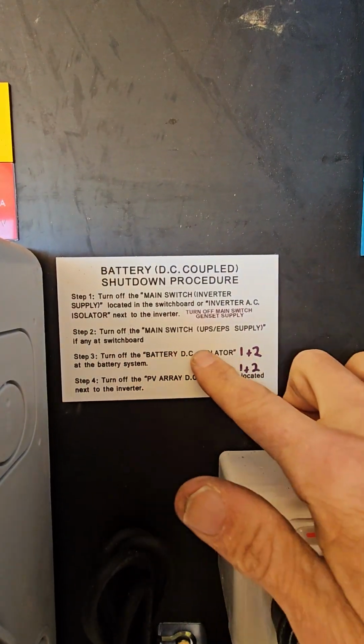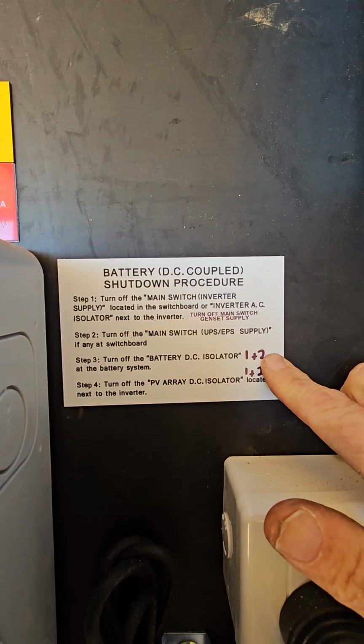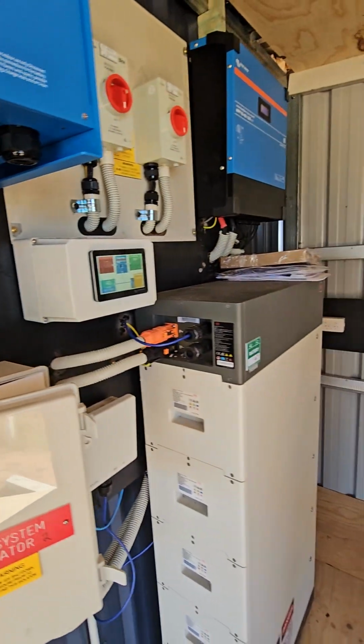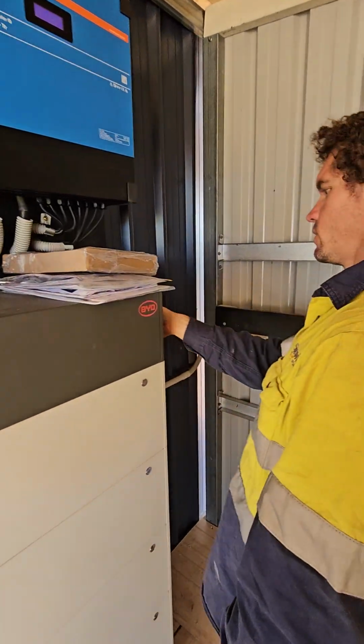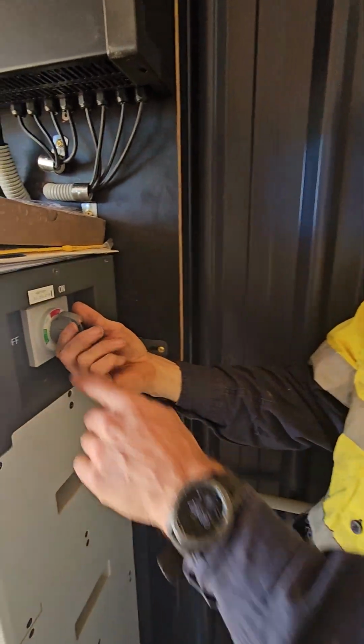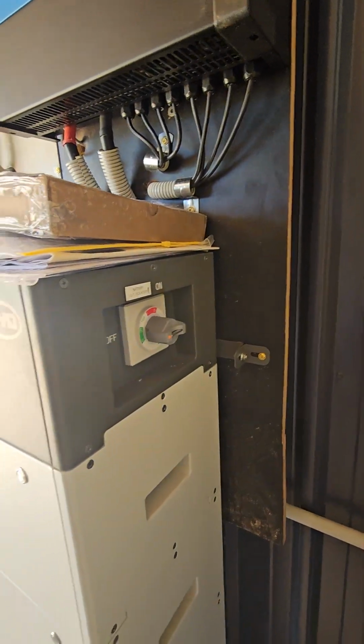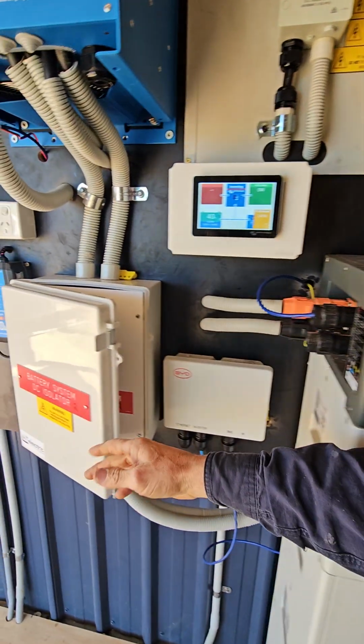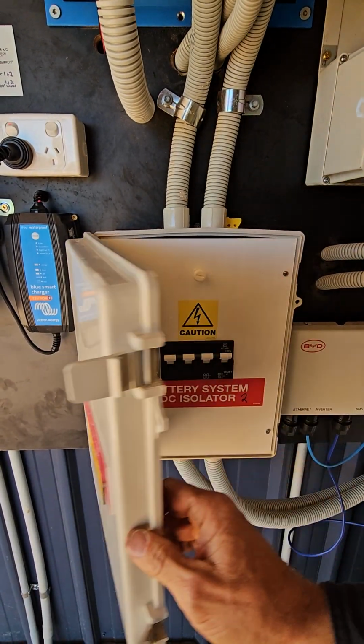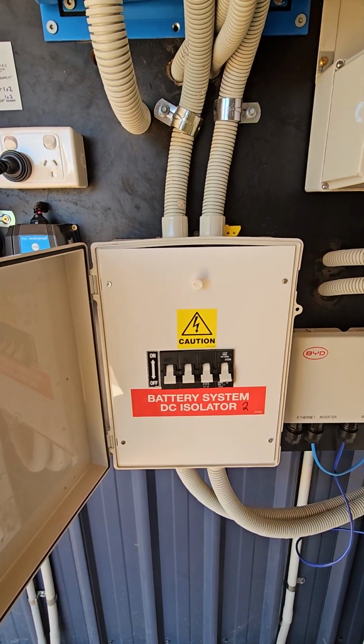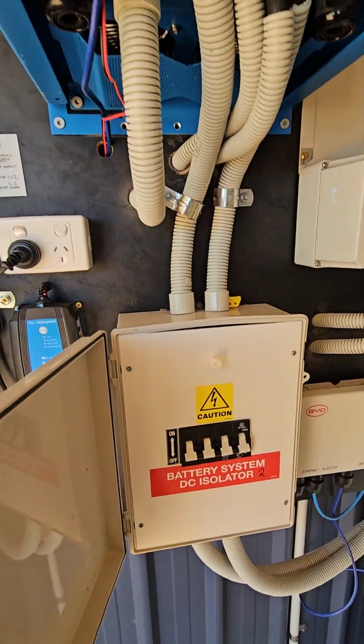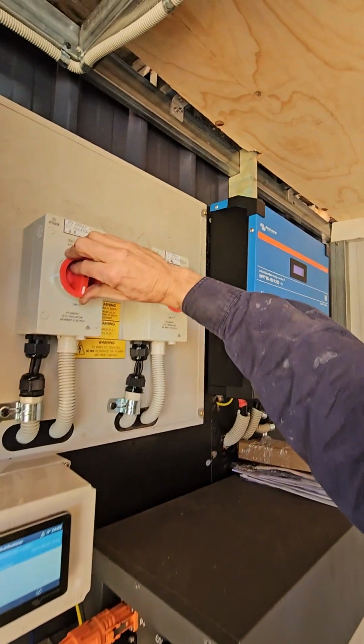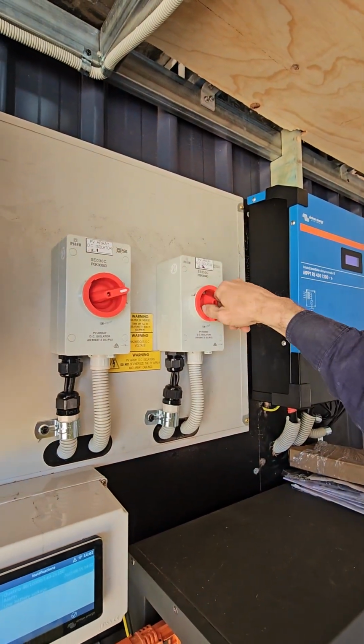Now we need to turn off battery system DC isolator 1 and 2. Main switch battery system DC isolator number 1 is over here - turn that one off. Main switch DC isolator number 2 is this big one in the box - turn that off. Then we turn off the PV array DC isolators, which are these 2 here. That's your full shutdown.